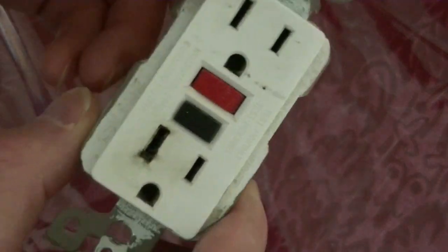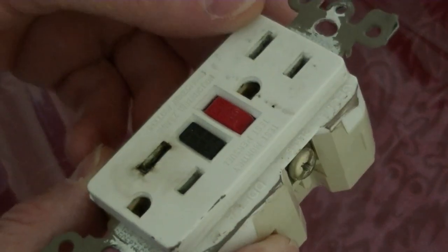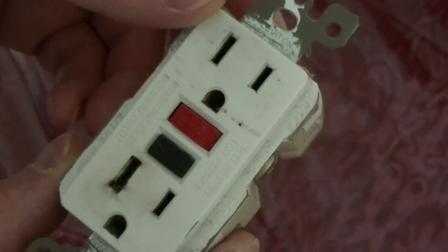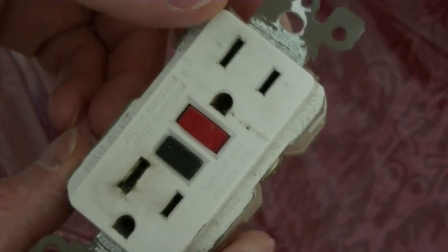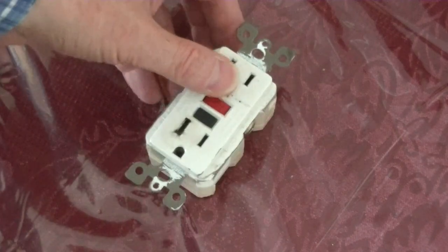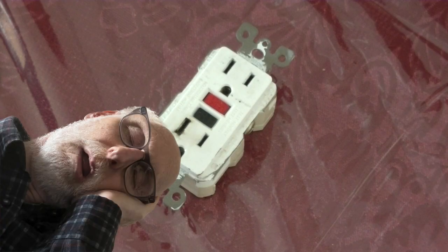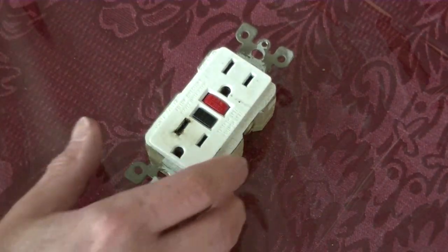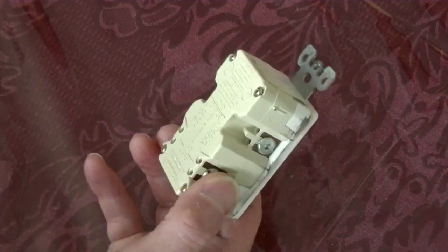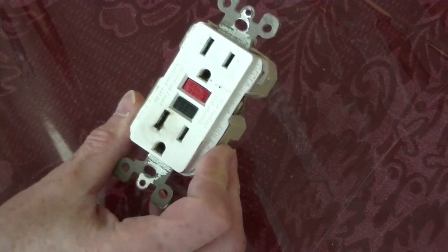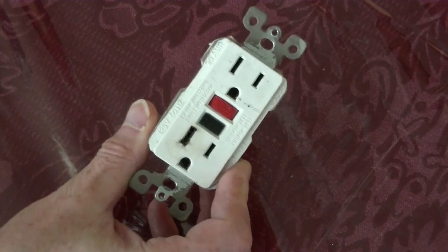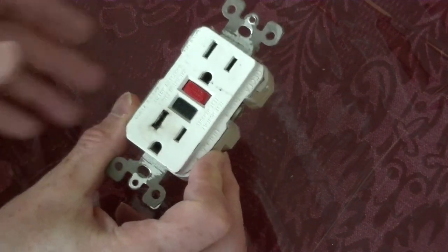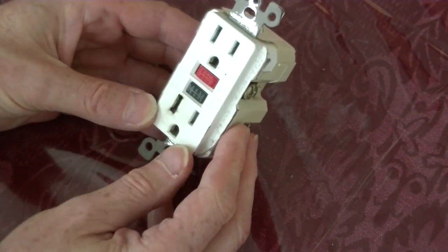Recently, Mrs. Brown plugged an appliance into a GFCI, that is, a ground fault circuit interrupter receptacle in her bathroom. There was a spark and a loud pop, and Mr. Brown was called to examine and replace the receptacle. I thought I'd use the opportunity to rip it apart to look inside. I'd never seen the inside of one before, and also explain how these deceptively simple devices protect people and property by detecting ground fault conditions.